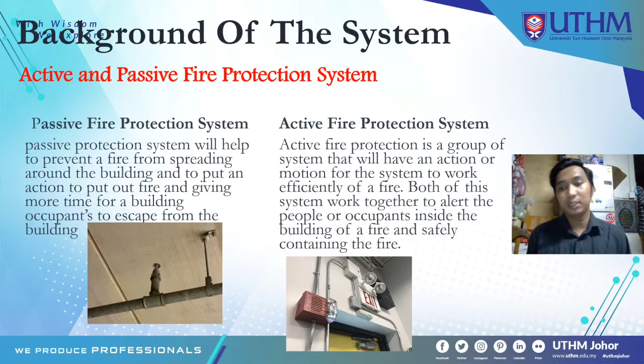Fire protection systems have two types. The passive protection system helps to prevent a fire from spreading around the building, giving more time for building occupants to escape and reducing the amount of damage; it is also a group of systems that compartmentalize the building through resistance in a wall or floor. Active fire protection, however, is a group of systems that have an action or motion for the system to work efficiently against a fire. Both systems work together to alert the people and occupants inside the building of a fire and safely contain the fire.